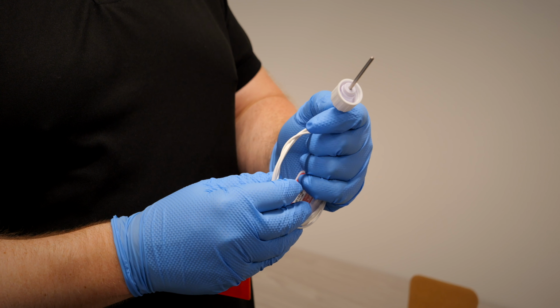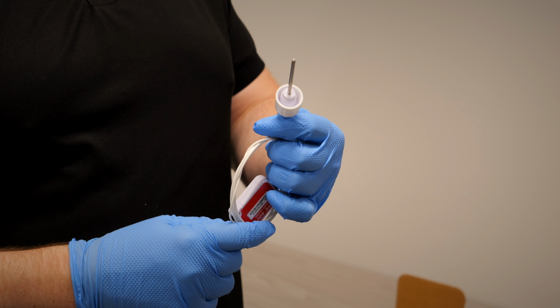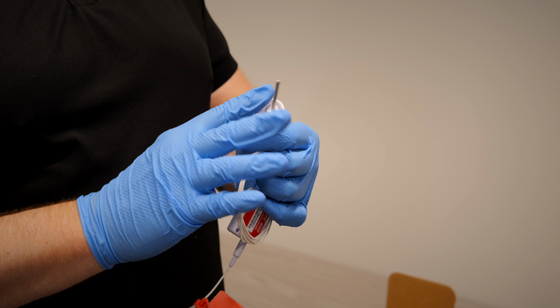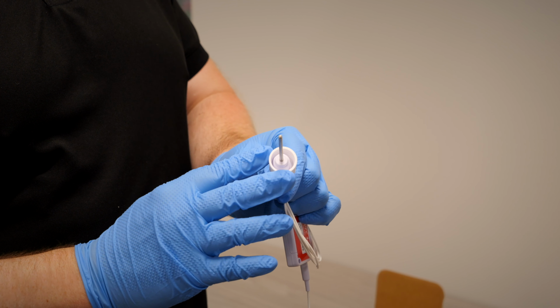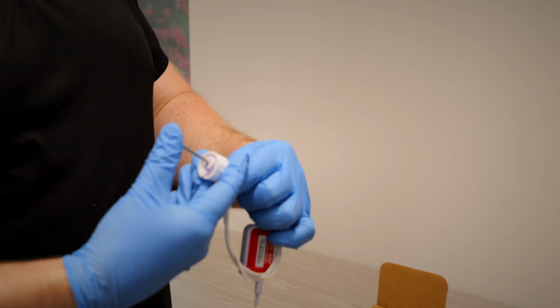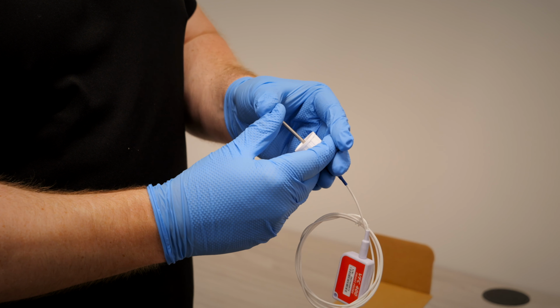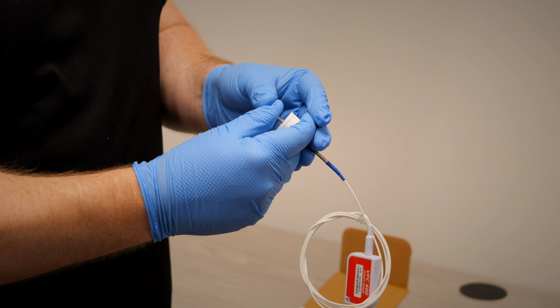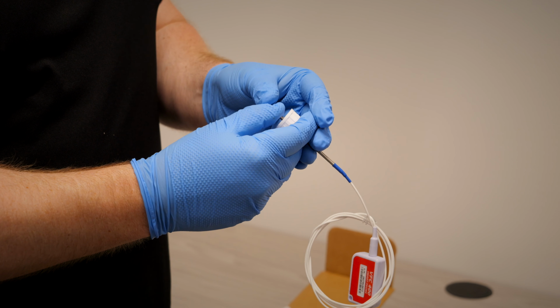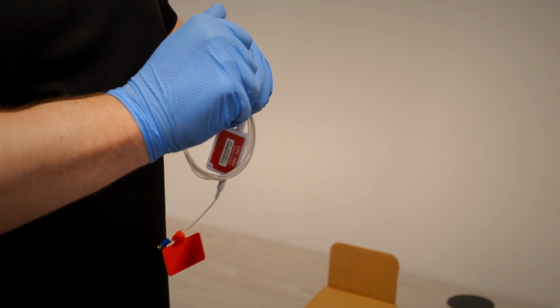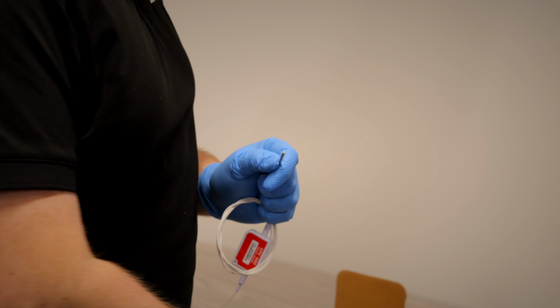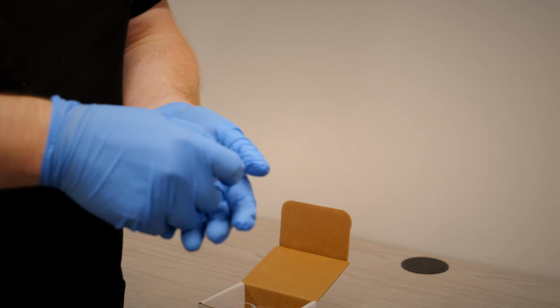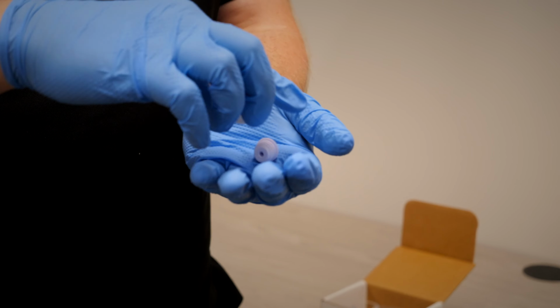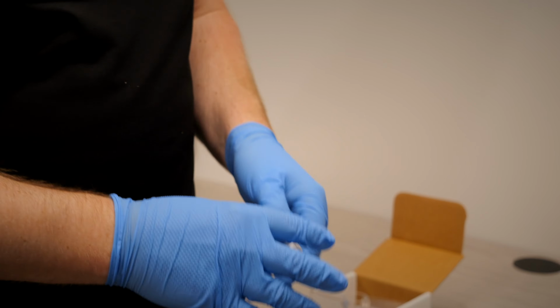For our installation, since we're using a lab grade refrigerator that does have a probe pass through, we will be removing the probe cap and seal prior to our installation. I find this is pretty much the easiest way to get them out without pulling on the probe cable too hard. Take that off, set our probe down here, and then we have our cap and our seal inside, and we'll set those aside. Next, we have our glycol buffer stand.